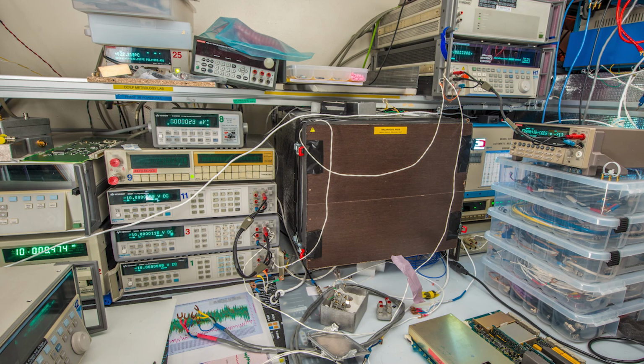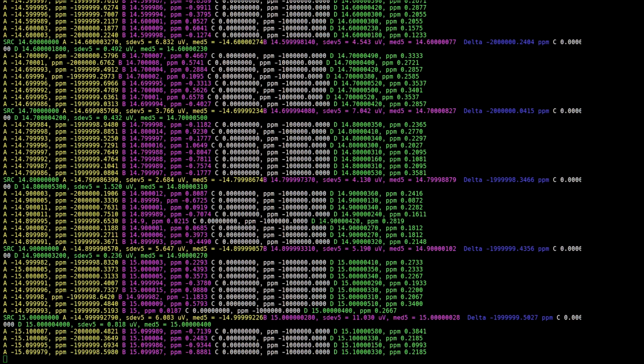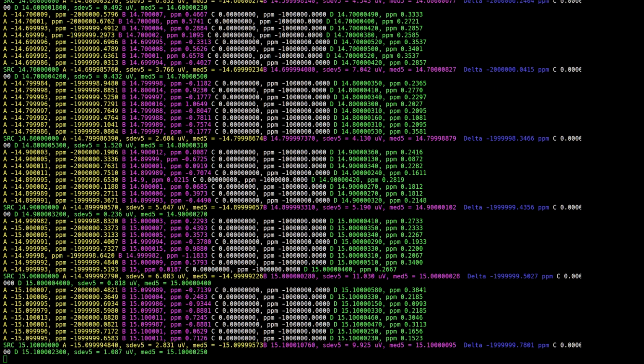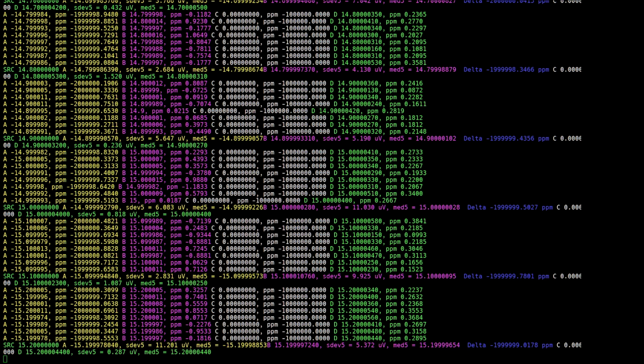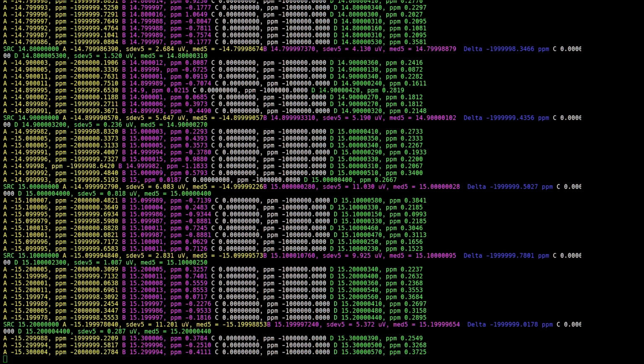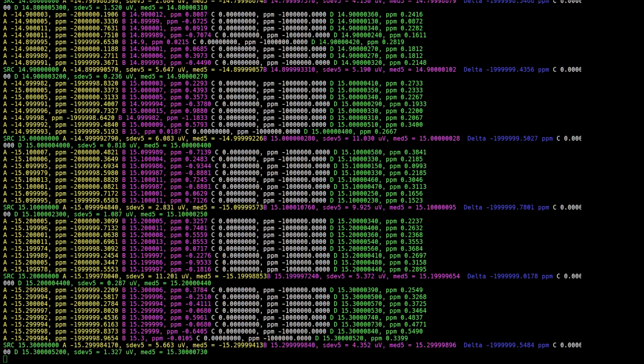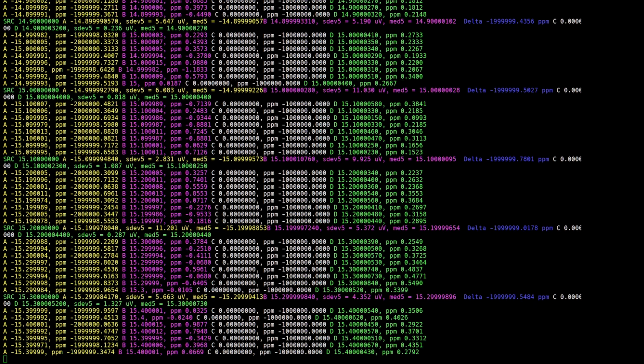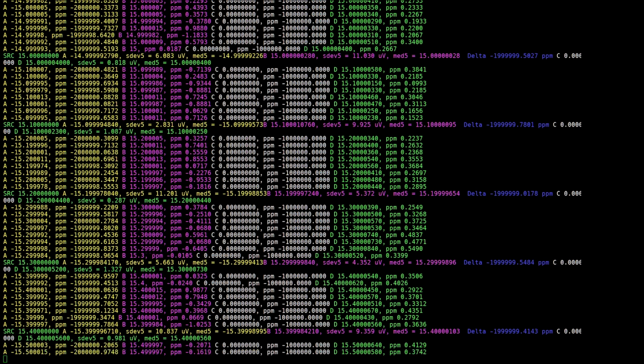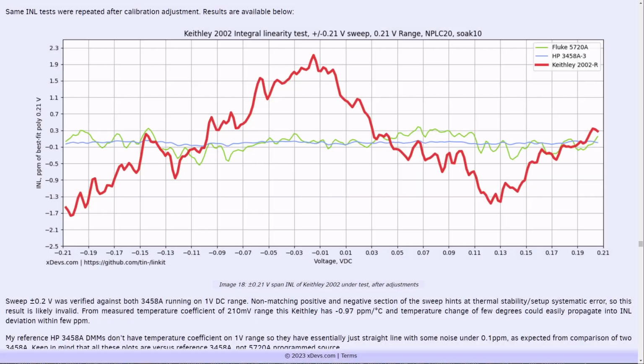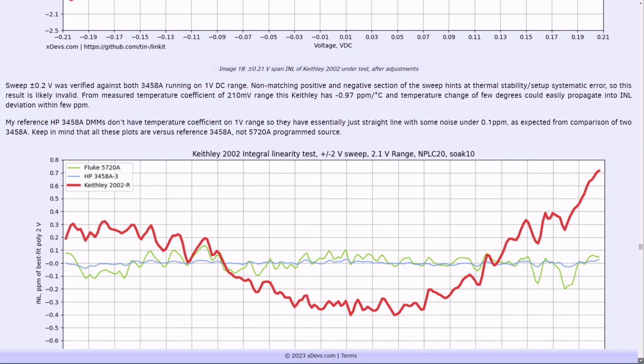So you can see reference 3458As and DMM on top right corner, together with the test 2002 in this particular verification. And here is the speed up screen capture of application that collects data points with 1% steps for particular range on both 3458A used as a reference and DUT instrument, in this case Keithley 2002. I will not focus on INL results too much in this video, but all the data is available in article, so be sure to check it out.